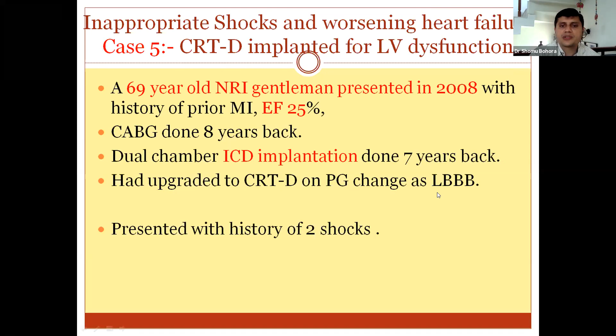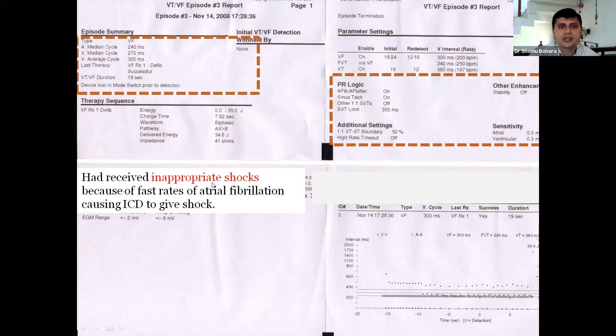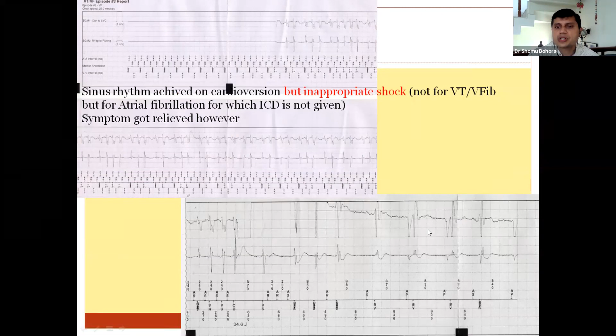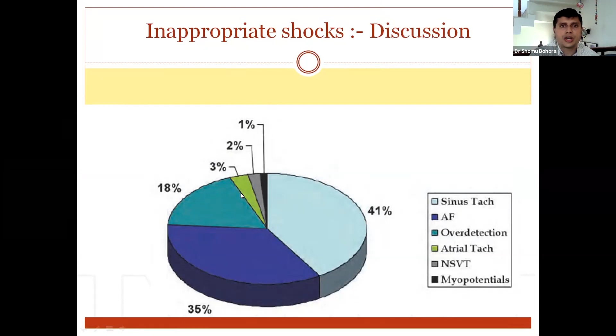And what you see here is the device was in mode switch prior to detection. That is also important. And what you see here is the SVT limit is 300 milliseconds, right? The differentiation is on, other SVTs are off, and stability is off. So this was the basic parameter set. What you see is an inappropriate shock because of fast rates of atrial fibrillation. So the atrial rate is higher than the ventricular rate, and the patient has received a shock which terminated the tachycardia. Importantly, 40% of inappropriate shocks are because of an atrial arrhythmia, which includes atrial fibrillation and atrial tachycardia. Around 40% would be for sinus tachycardia because it has not been programmed well. And 18% will be because of oversensing and other device related or external noise.